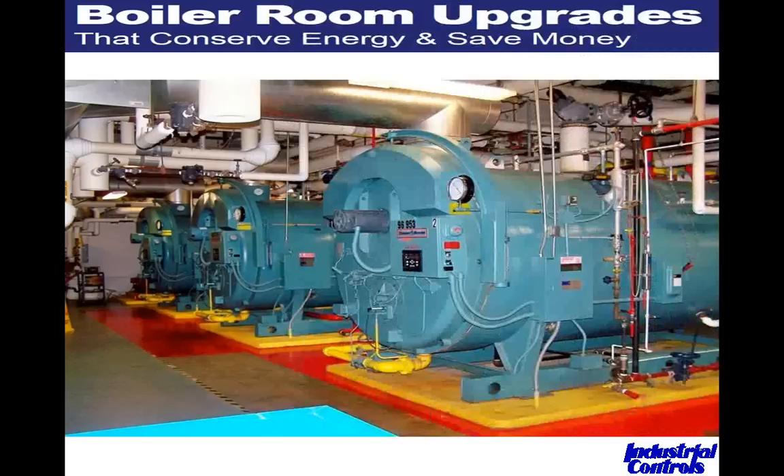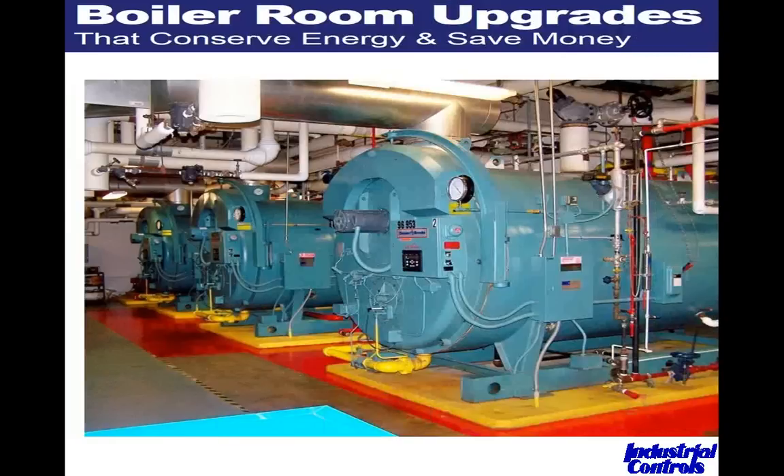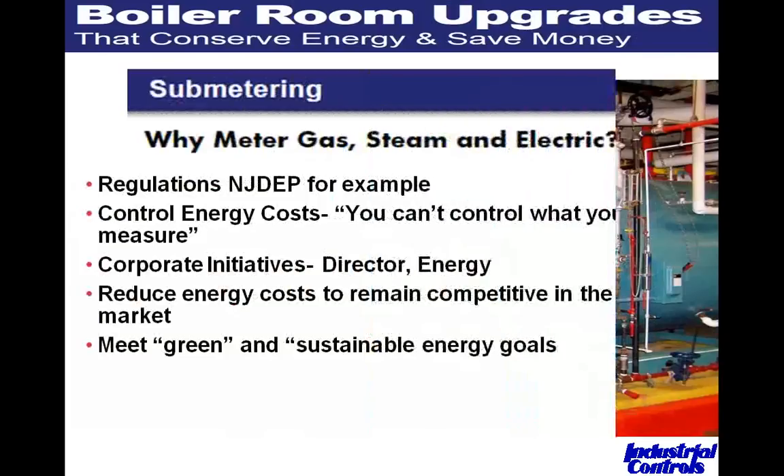Here's a picture of a job I worked on last year. This particular site had 17 boilers in five different locations — three of these are Cleaver Brooks 400 horsepower boilers. The customer wanted to put gas meters on each individual boiler, and we took the signals from those meters into five individual Honeywell paperless recorders. At the end of each month, the paperless recorder sends the gas usage for each of the 17 meters in the five locations to the environmental team for state reporting.